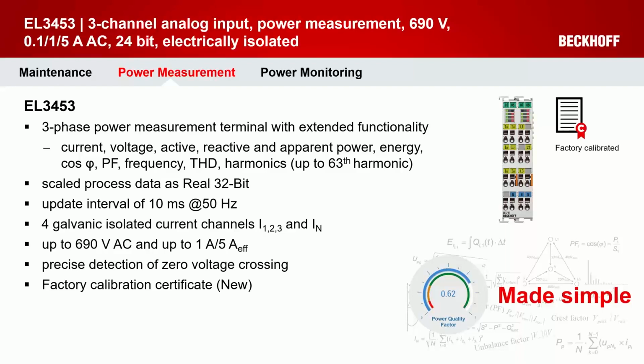The RMS update rate, true RMS, is the same as the grid period. It means 10 milliseconds at a 50 Hertz grid, to allow fast reaction, for example, for low voltage ride-through detection. This I will also explain in one of my later slides. Also, we have integrated statistic functions like minimum, maximum, and average calculation. This is all done by the terminal itself. With an extra fourth current channel, we are able to calculate neutral and earth fault current.